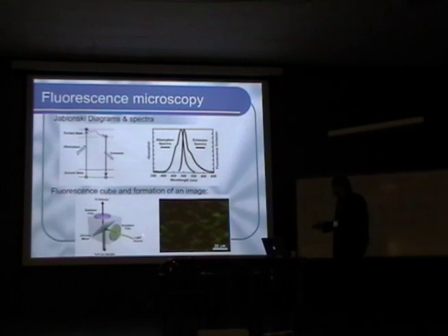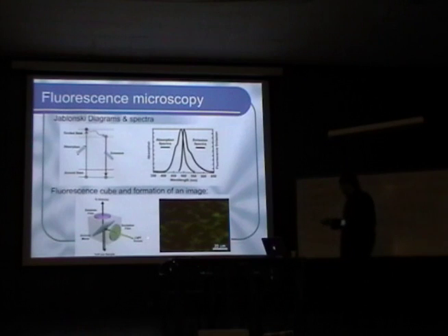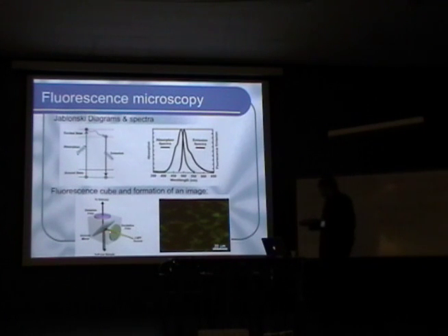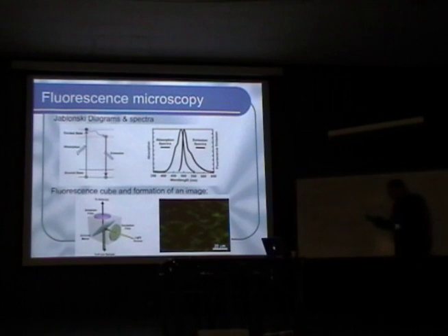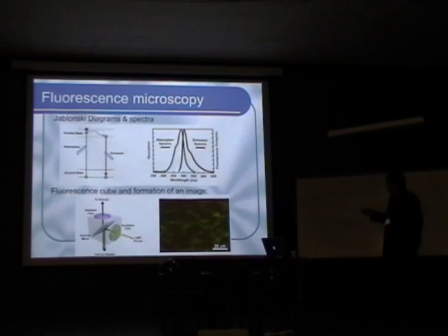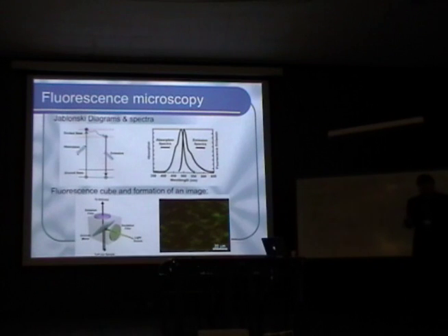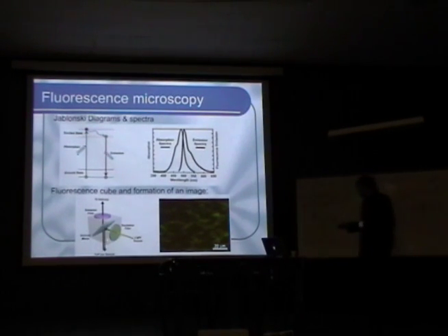If we have a light source that we use for excitation, which can be, for example, a white light source, an intense bulb, for example, of intense light, passing the excitation filter, we assure that the excitation light is at the wavelength at which the chromophore of interest is efficiently absorbing light. Then this light is reflected by the dichroic mirror to the sample.